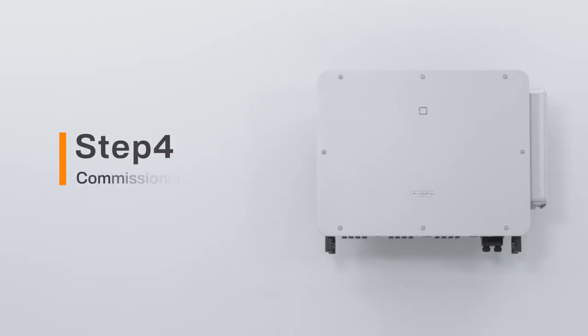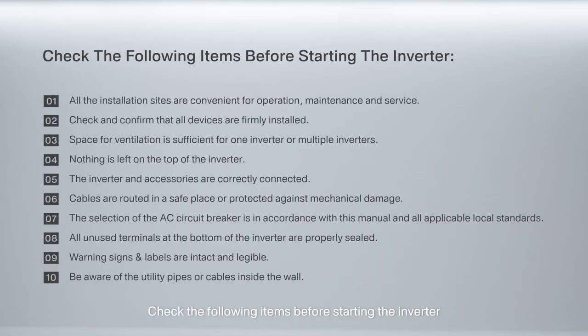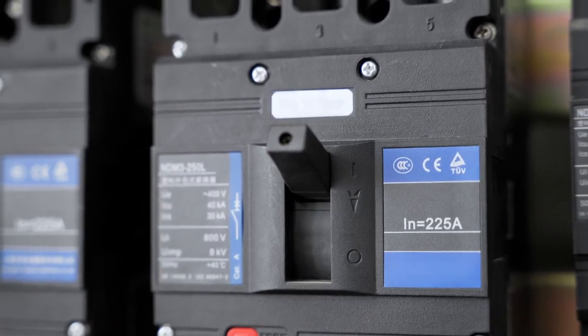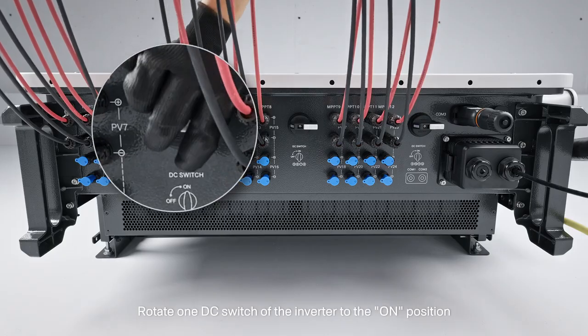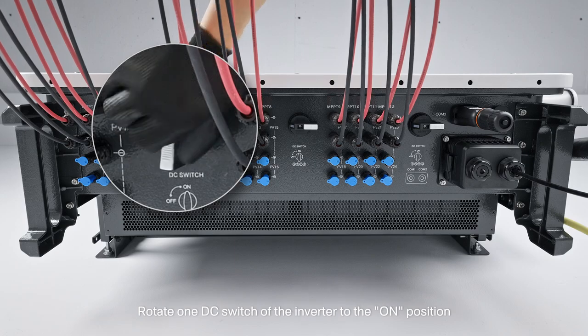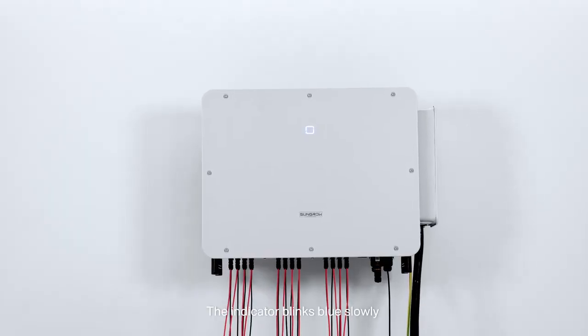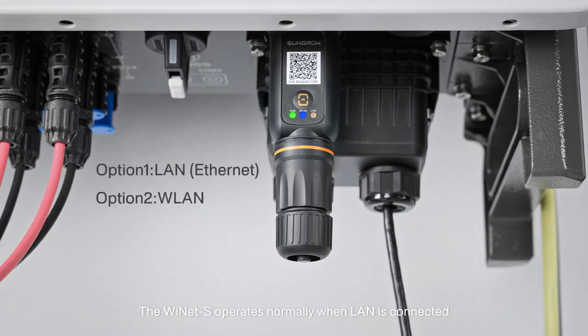Step 4. Commissioning. Check the following items before starting the inverter. Close the circuit breaker. Rotate one DC switch of the inverter to the on position. The indicator blinks blue slowly. The WiNet-S operates normally when LAN is connected and the indicators are in the above state.